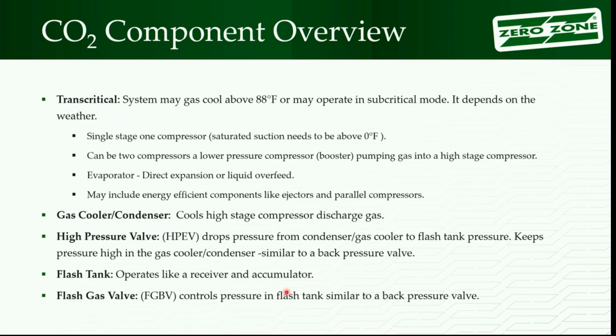When you work with the evaporators, a transcritical system doesn't necessarily tell you what the evaporator is doing. With a transcritical or a subcritical system, you could have direct expansion evaporators using an electronic expansion valve, or you could have flooded, pumped over feed evaporators. So again, those evaporators are kind of separated from what's going on on the high side of the system. The evaporators look for liquid out of the receiver and do their thing. So what you're doing up here doesn't necessarily drive what's going to be going on the low side of the system.